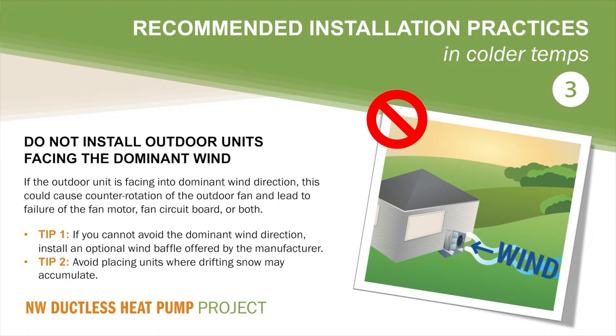The third practice is, do not install outdoor units such that they face the dominant wind direction. Some locations have a dominant wind direction, which means that at certain times of the year or during storm events, the wind will blow from a particular direction. If the outdoor unit faces into the dominant wind direction, this could cause counter rotation of the outdoor fan and ultimately lead to failure of the fan motor, fan circuit board, or both.